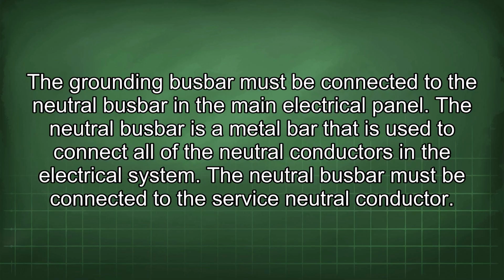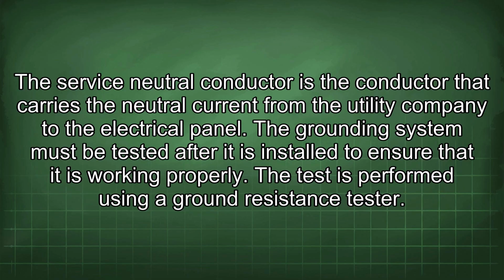The grounding busbar must be connected to the neutral busbar in the main electrical panel. The neutral busbar is a metal bar that is used to connect all of the neutral conductors in the electrical system. The neutral busbar must be connected to the service neutral conductor. The service neutral conductor is the conductor that carries the neutral current from the utility company to the electrical panel.